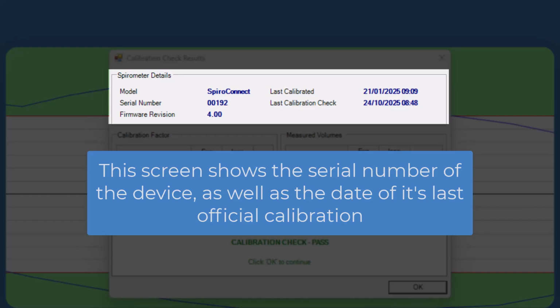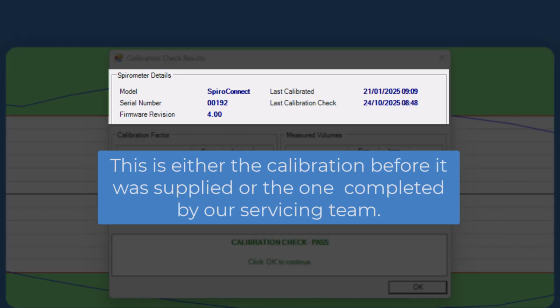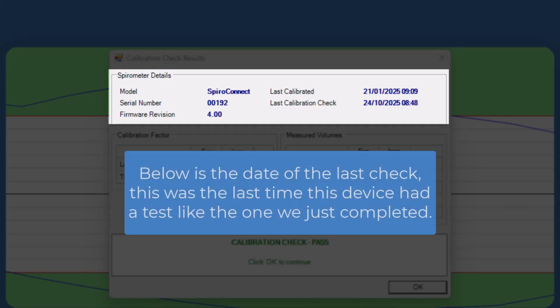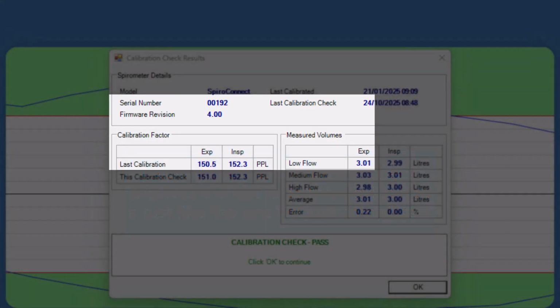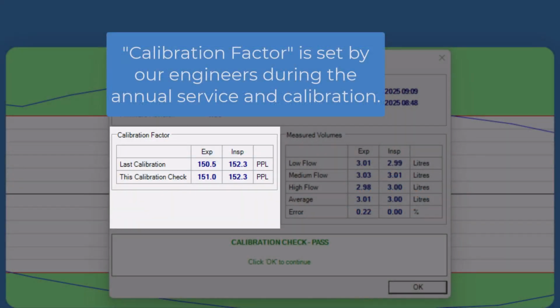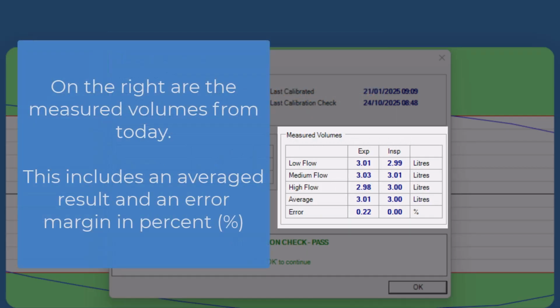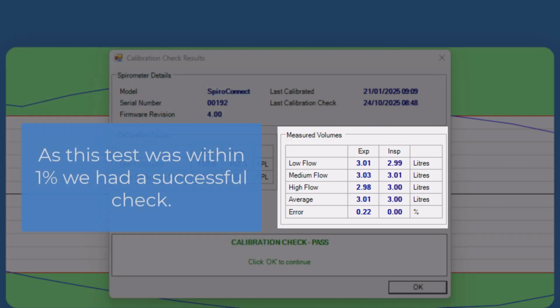This screen shows the serial number of the device, as well as the date of its last official calibration. This is either the calibration before it was supplied or the one completed by our servicing team. Below is the date of the last check. This was the last time this device had a test like the one we just completed. Calibration factor is set by our engineers during the annual service and calibration. On the right are the measured volumes from today. This includes an averaged result and an error margin in percent. As this test was within 1%, we had a successful check.